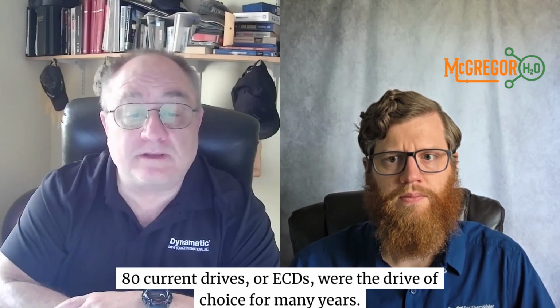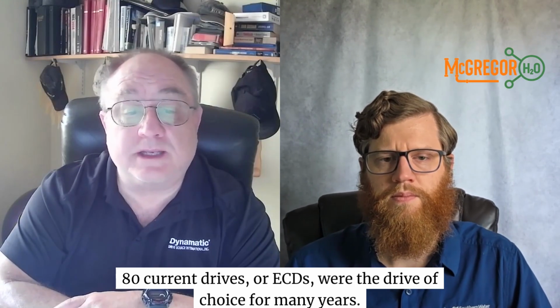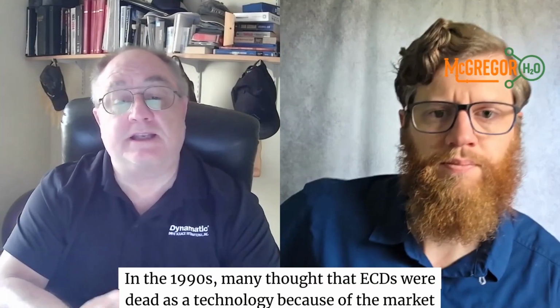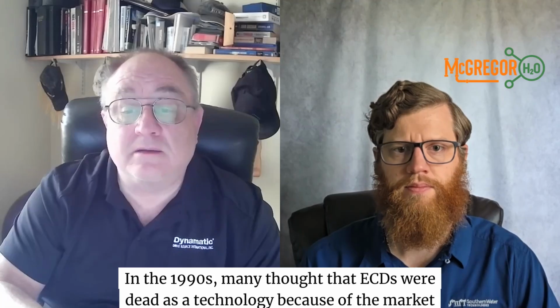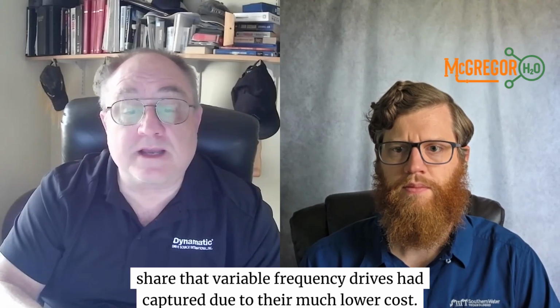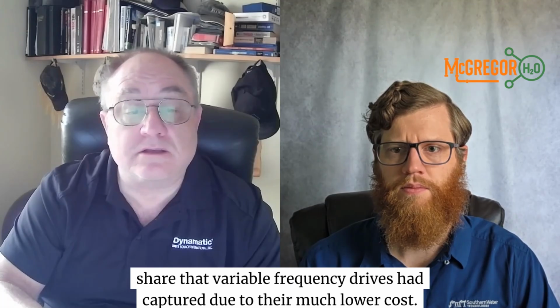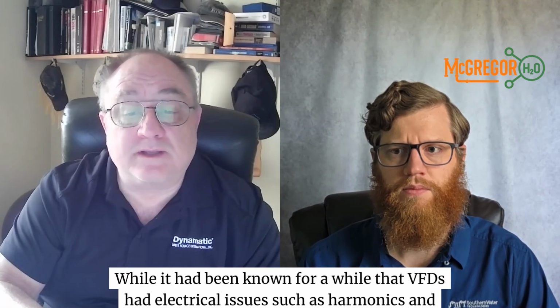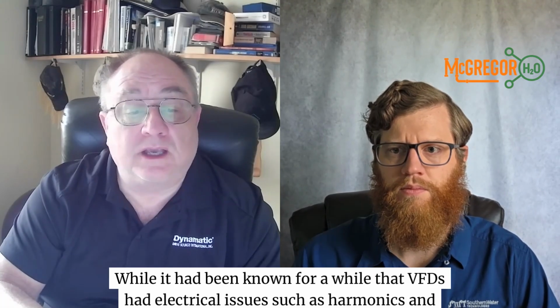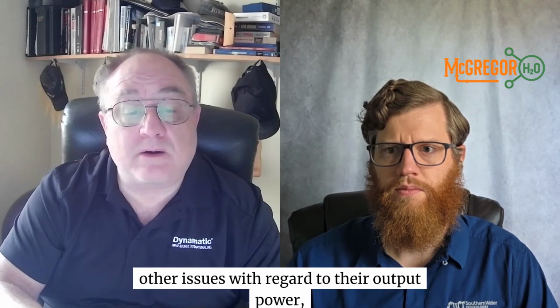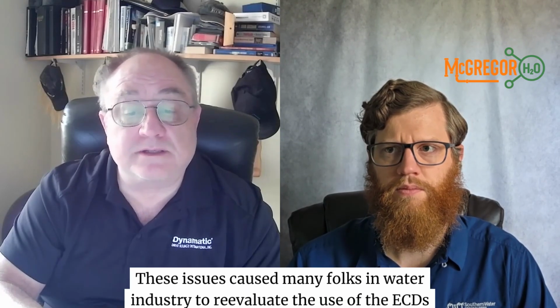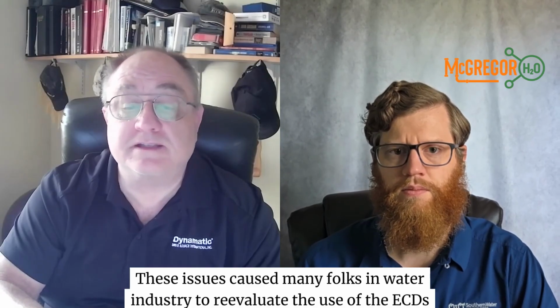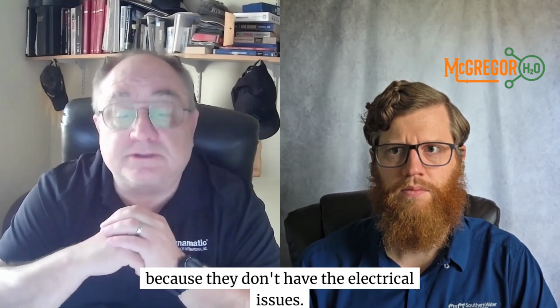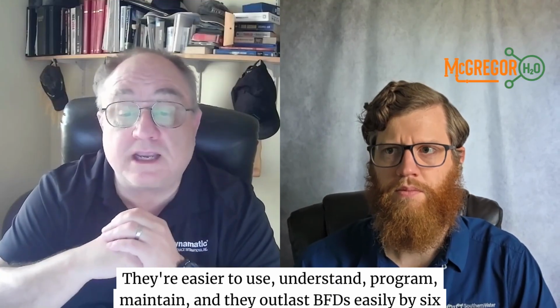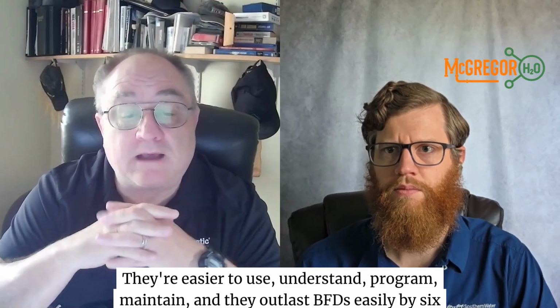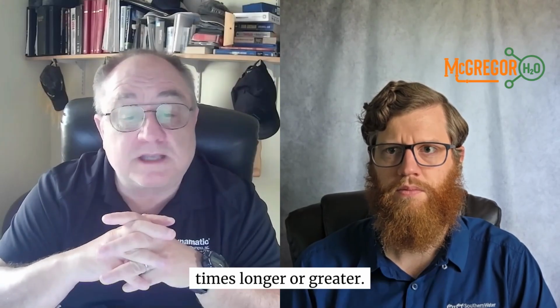Eddy current drives, or ECDs, were the drive of choice for many years. In the 90s, many thought that ECDs were dead as a technology because of the market share that variable frequency drives had captured due to their much lower cost. While it had been known for a while that VFDs had electrical issues such as harmonics and other issues with regard to their output power, these issues caused many folks in the water industry to reevaluate the use of ECDs because they don't have the electrical issues. They're easier to use, understand, program, maintain, and they outlast VFDs easily by 6 times longer or greater.